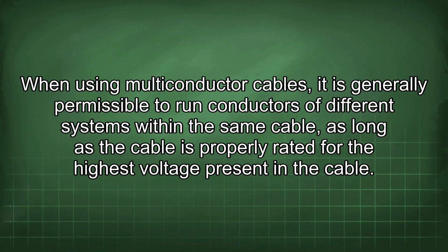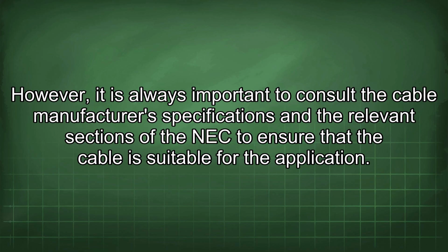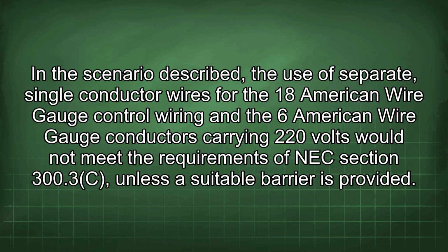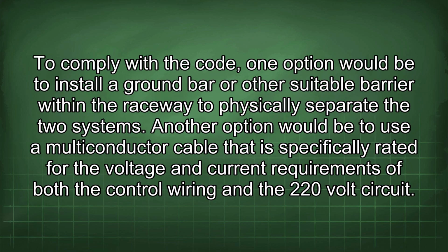When using multi-conductor cables, it is generally permissible to run conductors of different systems within the same cable, as long as the cable is properly rated for the highest voltage present in the cable. However, it is always important to consult the cable manufacturer's specifications and the relevant sections of the NEC to ensure that the cable is suitable for the application. In the scenario described, the use of separate, single conductor wires for the 18 American wire gauge control wiring and the 6 American wire gauge conductors carrying 220 volts would not meet the requirements of NEC Section 300.3(C) unless a suitable barrier is provided. To comply with the code, one option would be to install a ground bar or other suitable barrier within the raceway to physically separate the two systems.